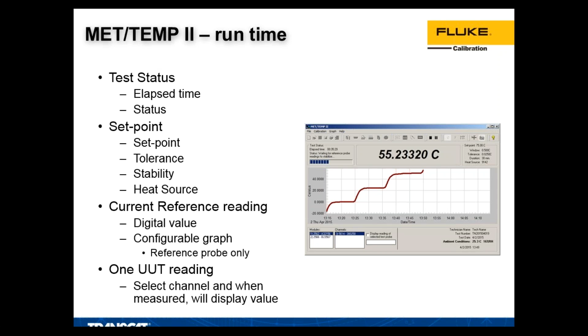As mentioned before, you can generate all of your calibration coefficients for PRTs, thermocouples, and thermistors. You can do it in ITS-90, Callendar-Van Dusen, or IPTS-68. For thermocouples you can use the appropriate methods, and for thermistors you can do the Steinhart-Hart equation.